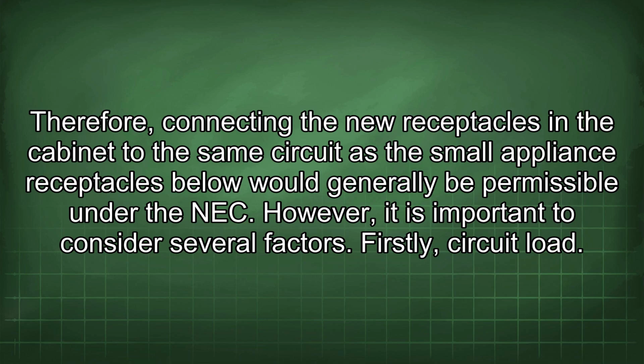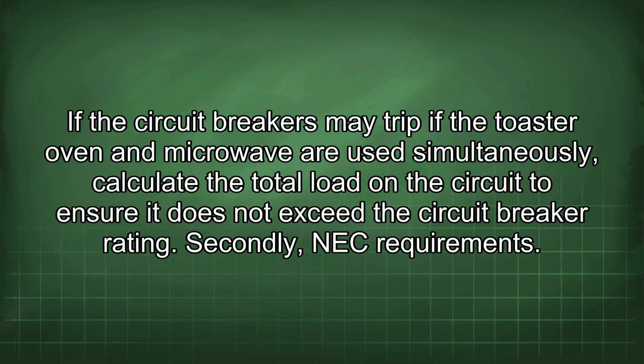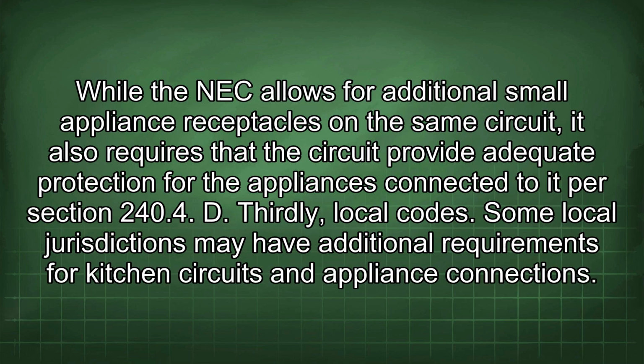Firstly, circuit load. If the circuit breakers may trip if the toaster oven and microwave are used simultaneously, calculate the total load on the circuit to ensure it does not exceed the circuit breaker rating. Secondly, NEC requirements. While the NEC allows for additional small appliance receptacles on the same circuit, it also requires that the circuit provide adequate protection for the appliances connected to it per section 240.4. Thirdly, local codes. Some local jurisdictions may have additional requirements for kitchen circuits and appliance connections.